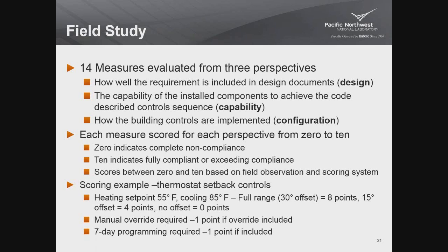And obviously, you could have the first two be fine. If the configuration perspective isn't very good, you're not going to get the energy savings. For each measure and each perspective, we scored them from 0 to 10. 0 meant that it was completely non-compliant, absent from the building or the design altogether. 10 indicated it was fully compliant or it exceeded compliance. If it exceeded compliance, it got a 10 as well. And then scores between 0 and 10 were based on the condition that was observed out in the field and a scoring system that we developed for each of the measures.